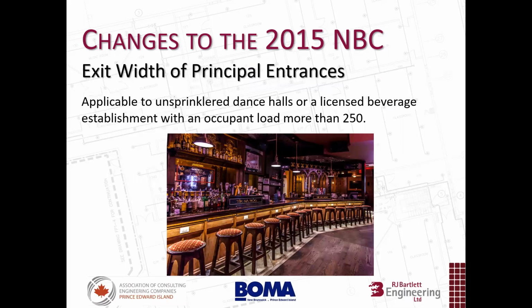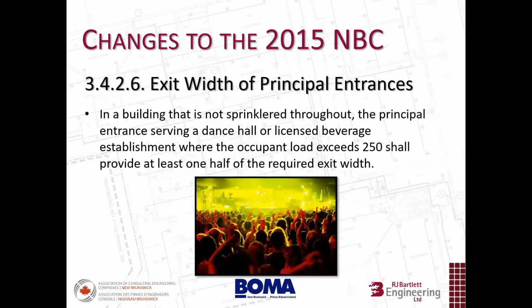Here we have a new requirement to the 15 code. It's applicable to unsprinkled dance halls or licensed beverage establishments with an occupant load of more than 250 people. The requirement is that if the building is not sprinkled throughout, the principal entrance serving the dance hall or licensed beverage establishment where the occupant load exceeds 250 shall provide at least 1/2 of the required exit width.